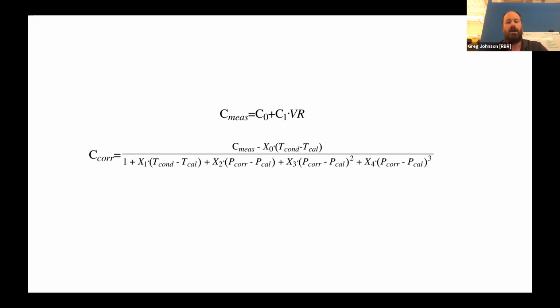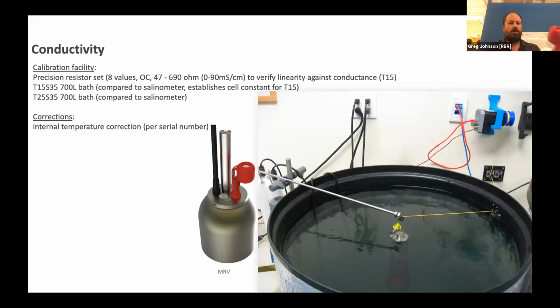the voltage ratio. However, the conductivity cell has a couple of sensitivities to temperature and pressure. And so one is that the ferrites themselves and the coil assembly behave slightly differently at different temperatures. And that's why we calibrate that thermistor in step 1. And the second is that just like an electrode-based cell, we need to convert from what we can measure, which is conductance, in Siemens, if you like, to conductivity, which is Siemens per meter, or as we do it, millisiemens per centimeter. We find it an easier unit to work with. And so we need to establish what is known as the cell constant that converts from conductance to conductivity. So how do we do that?